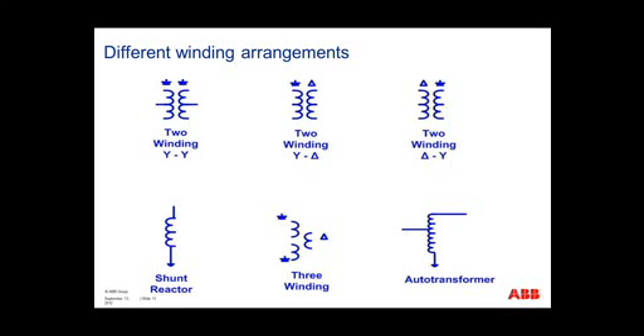Different winding arrangements that you can have for your transformer. You can have a Wye-Wye, which is a two-winding transformer, a two-winding Wye-Delta, two-winding Delta-wye, a shunt reactor, a three-winding transformer, Wye-Wye-Delta, or you can have an auto transformer.